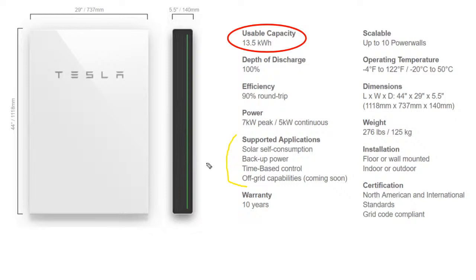Tesla focused on making a grid-tied inverter rather than an off-grid inverter, and it's scalable up to 10 Powerwalls. That's a really important feature when selecting a battery inverter, because not all battery inverters can operate alongside other manufacturers' equipment, or even alongside their own manufacturer's other equipment. The problem with all-in-one inverter systems is sometimes not all of those inverters are stackable. When you're working with grid-tied, bidirectional battery inverters capable of outflowing onto the grid, most are stackable within their own ecosystem. So a Tesla is stackable with another Tesla, a Schneider is stackable with another Schneider, but not necessarily vice versa.